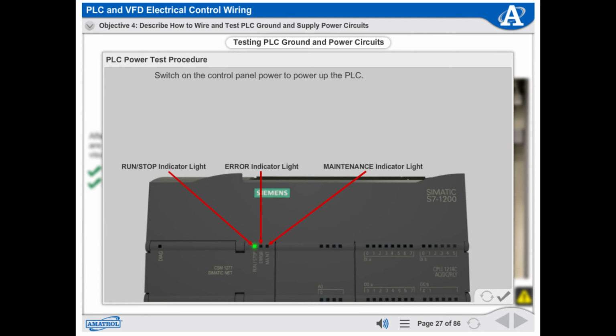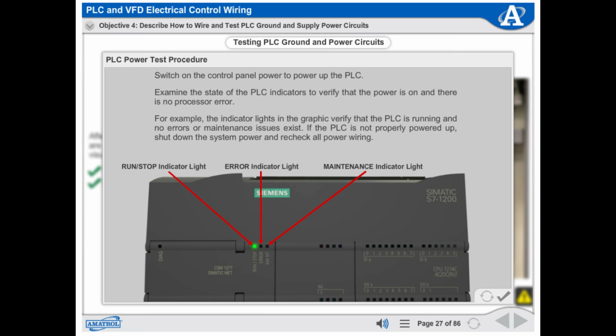Switch on the control panel power to power up the PLC. Examine the state of the PLC indicators to verify that the power is on and there is no processor error. For example, the indicator lights in the graphic verify that the PLC is running and no errors or maintenance issues exist. If the PLC is not properly powered up, shut down the system power and recheck all power wiring.